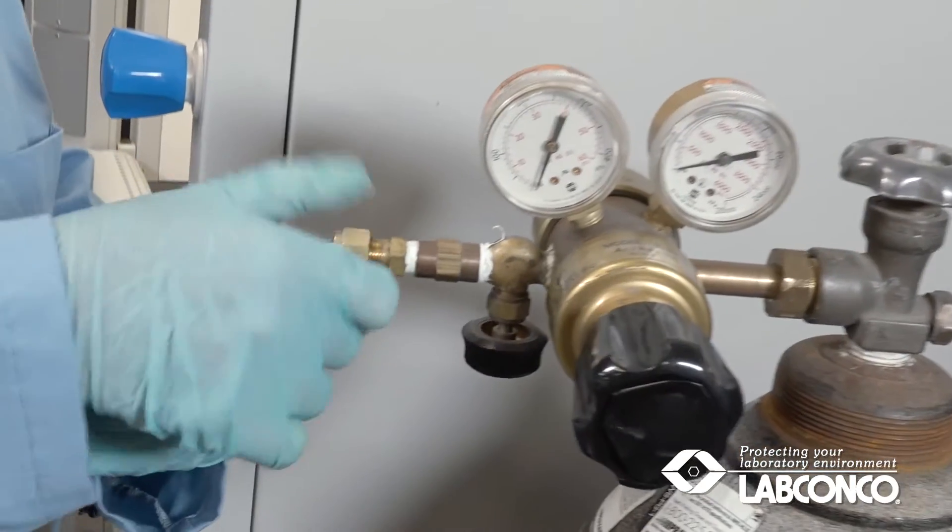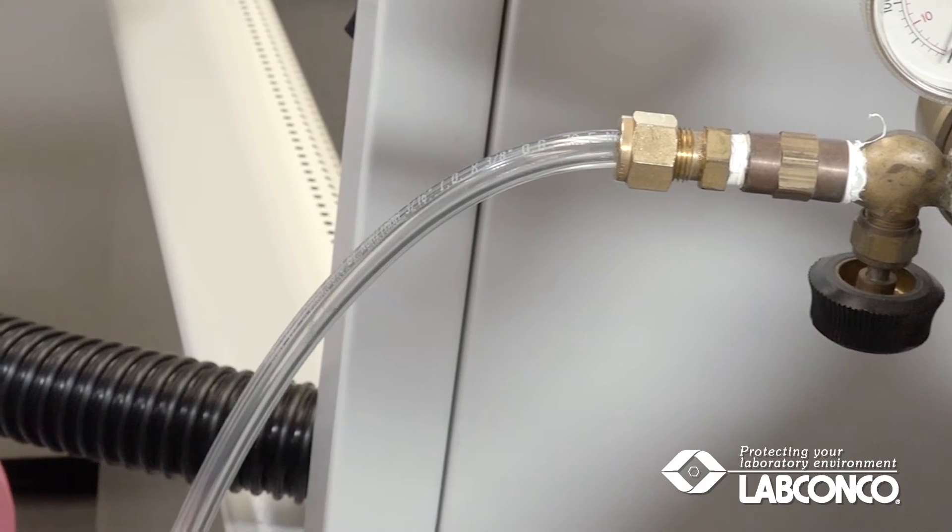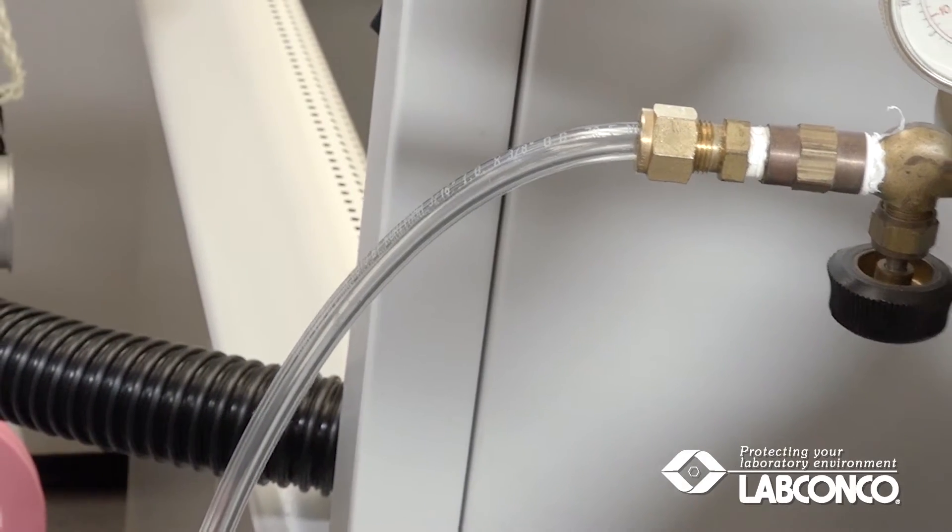Alternately, a compression fitting may be used that is suitable for a hose with a 3/8 inch outside diameter and a 1/4 inch inside diameter.